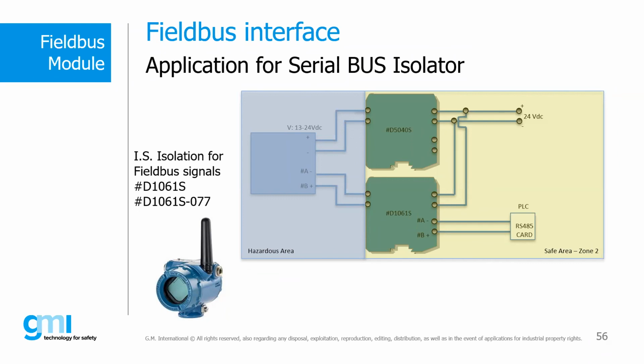And again, both the Profibus DP communication protocol and user-defined protocols are supported at baud rates from 1.2 kilobits per second to 1.5 megabits per second for Profibus DP, and from 1.2 kilobits per second up to 115.2 kilobits per second for the RS232 protocol. The unit provides the line termination capability on both hazardous and safe sides.